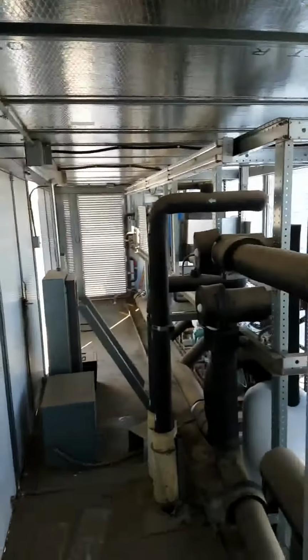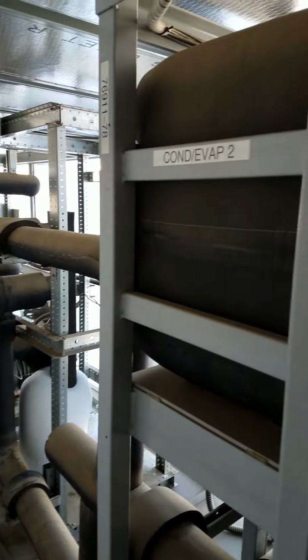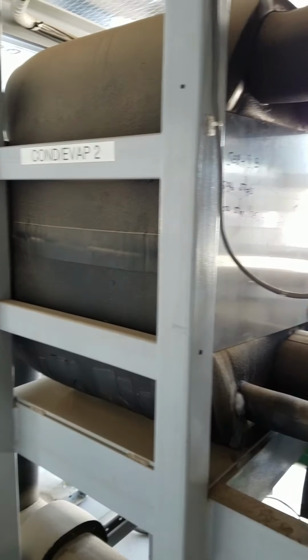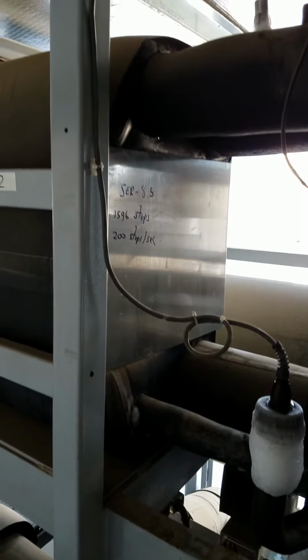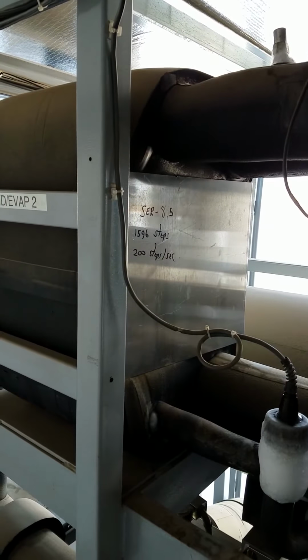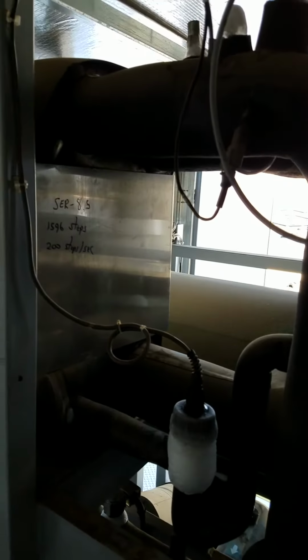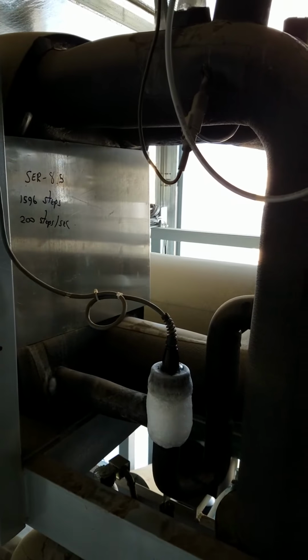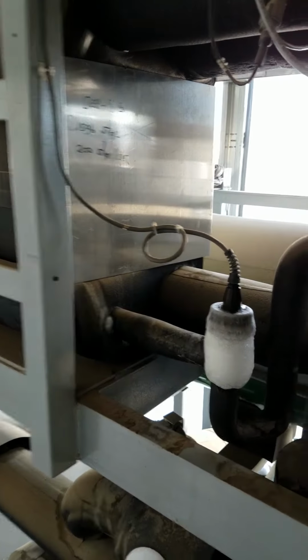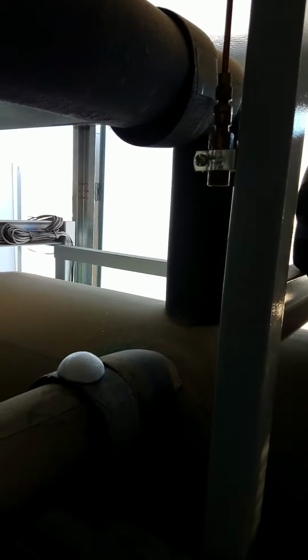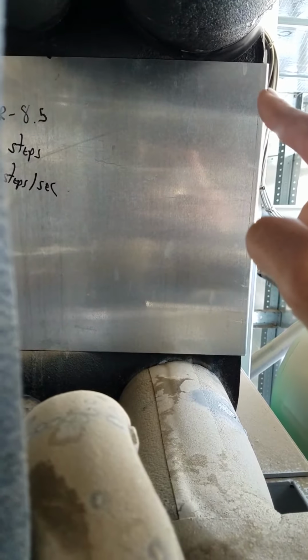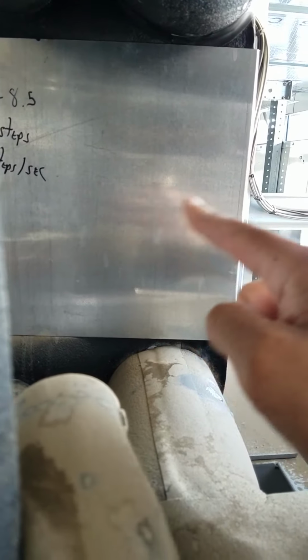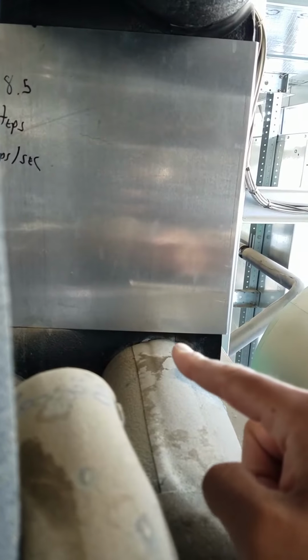Okay, now I'm inside the rack. Popped in that little door off to the left. Walked over here. Got your condenser evap 2. It's your chiller. Chills the refrigerant, flows through. It's like a subcooler. That's all it basically is. It condenses the CO2 vapor to a liquid. So you can see the outlet pulls the vapor out into one side of the plate, trickles down into a liquid. It's all gravity fed.